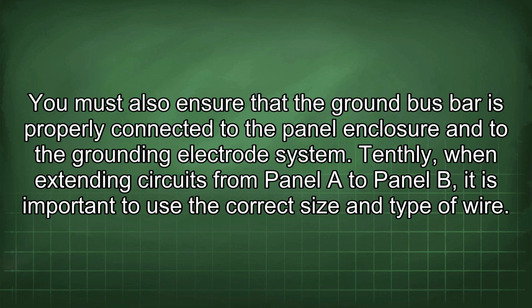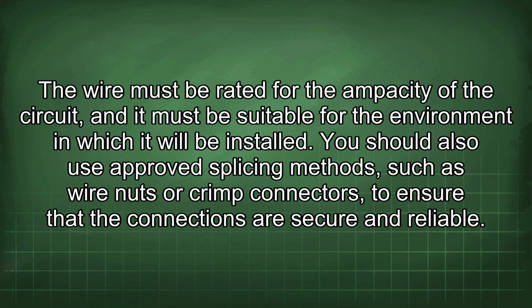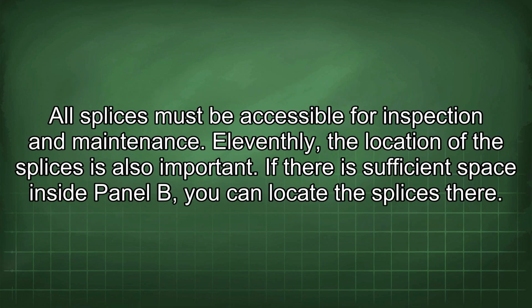and type of wire. The wire must be rated for the ampacity of the circuit, and it must be suitable for the environment in which it will be installed. You should also use approved splicing methods such as wire nuts or crimp connectors to ensure that the connections are secure and reliable. All splices must be accessible for inspection and maintenance.